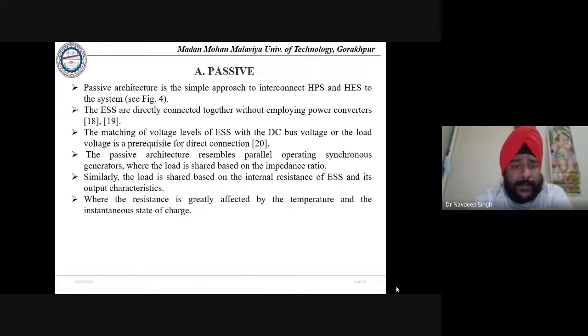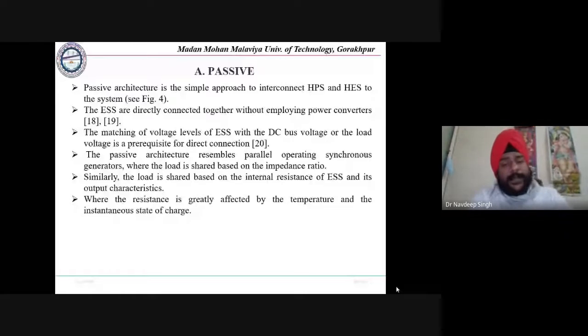If the impedance ratio is not the same, the parallel combination will not be possible, because losses will be there. If the impedance ratio is high for a system, the KVA rating of the system will differ. If a system has a high impedance ratio, the KVA rating requirement of the system is high. So it is more complicated to match the impedance ratio for a passive architecture configuration.